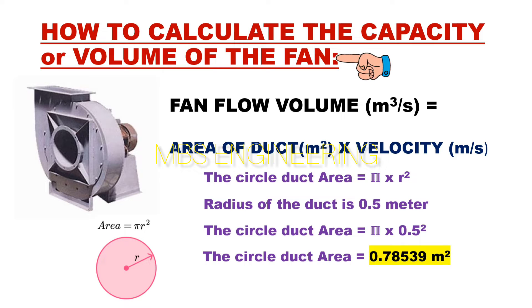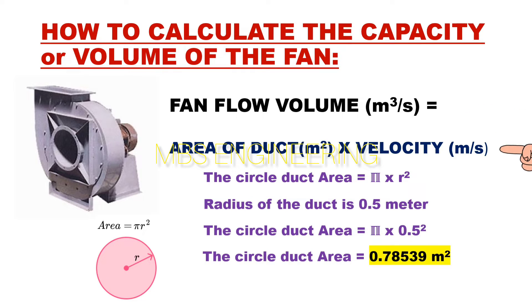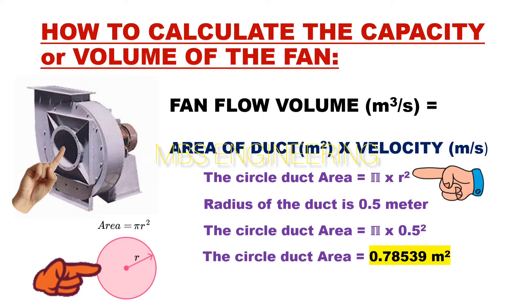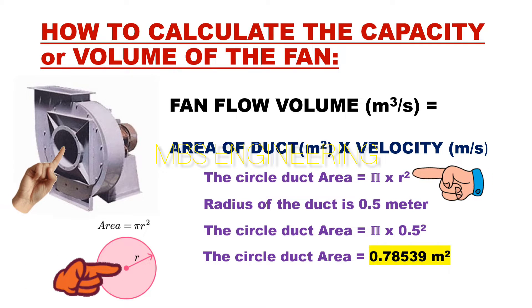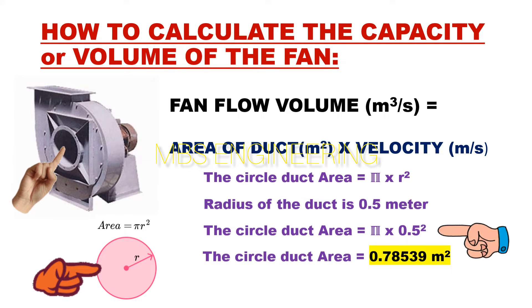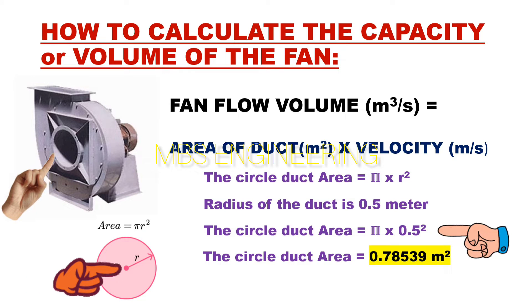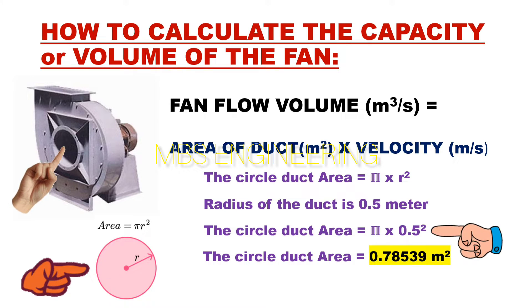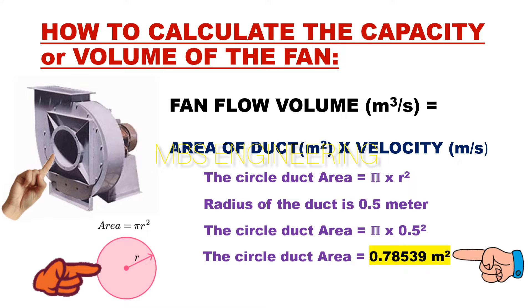The capacity or volume of the fan is equal to the velocity multiplied by the suction ducting area. First, we will calculate the suction ducting area of the fan. Since the fan suction area is circular, the suction ducting area is equal to pi times r squared. The radius of the duct is 0.5 meters, so the suction ducting area is pi × 0.5² = 0.78539 square meters.